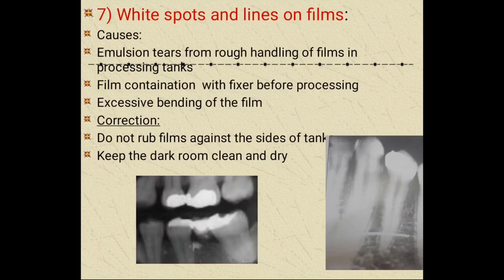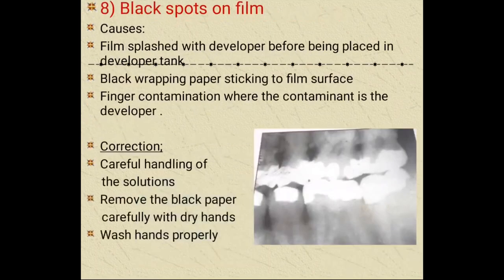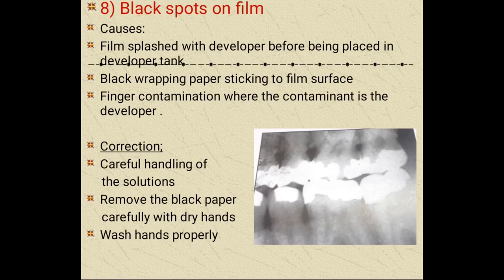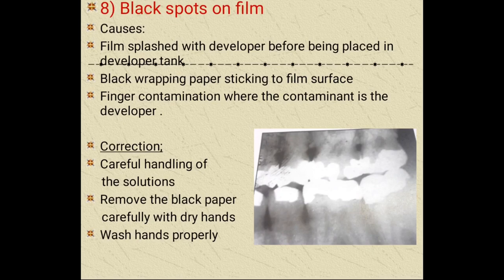Black spots on the film are caused by film being splashed with developer before being placed in the developer tank, black wrapping paper sticking to the film surface, or finger contamination where the contaminant is developer. Correct by careful handling of the solution, removing the black paper carefully with dry hands, and washing hands properly. Black lines are caused by static electricity — electrical discharges that produce visible light — occurring on the surface of the emulsion when film is removed rapidly from the interleaving paper.